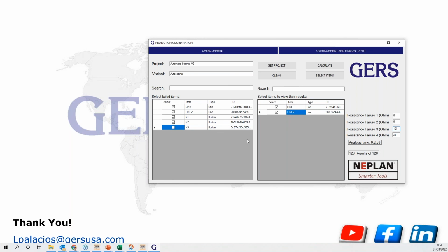But these applications have automated all the simulations. We have, for example, we selected these elements. So for each element, we will work with 3-phase fault, 1-phase fault, 2-phase fault, and for each fault, we have to see, yeah, what is the short circuit level when we have a variation of the resistance failure.